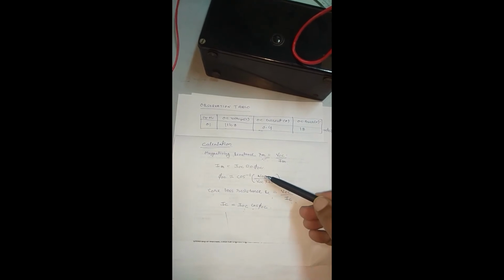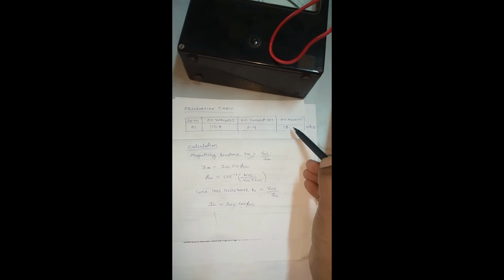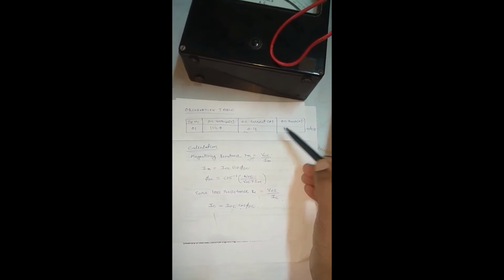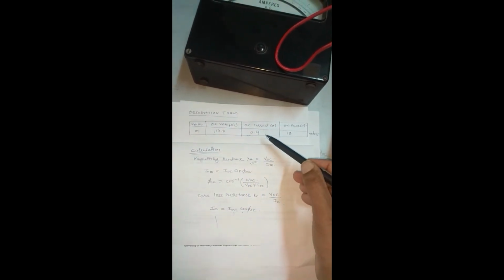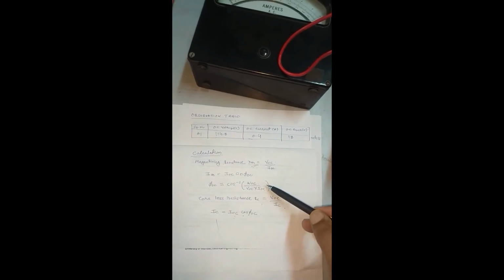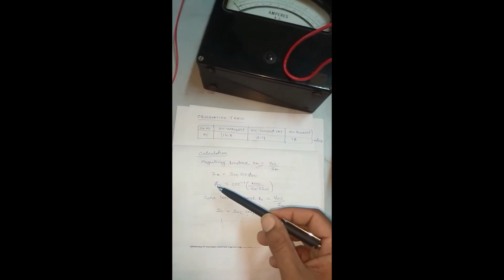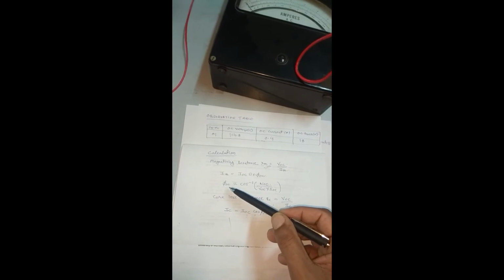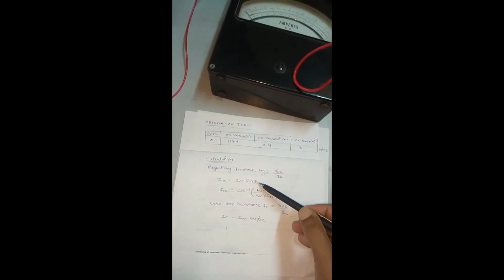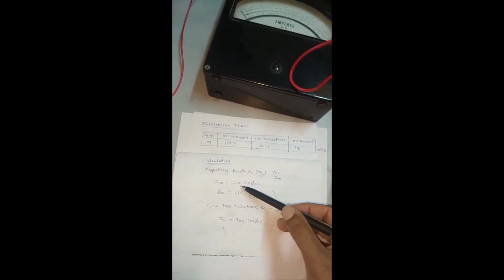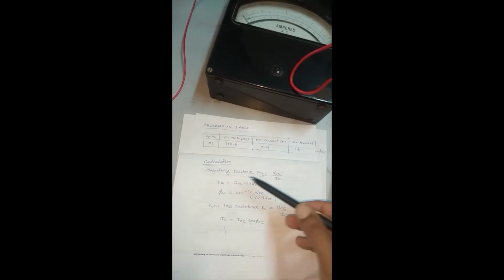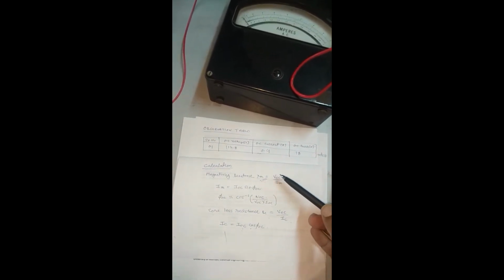WOC is the power measured during this test, so that is with us. We have VOC, we have IOC. Substitute these values, do the math, and you will find the power factor angle. Then substitute its value and the value of IOC, and you will get Im. So Xm is obtained using this equation.